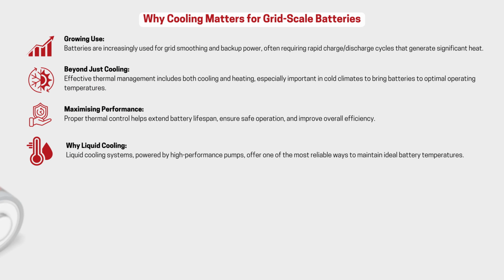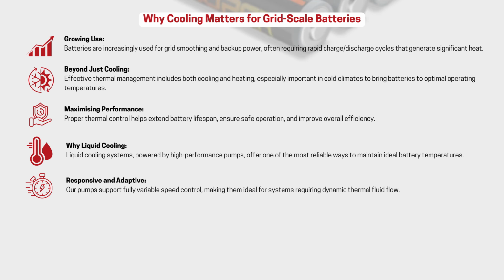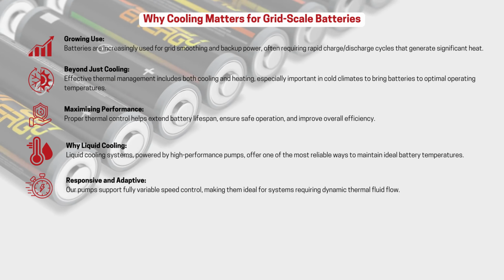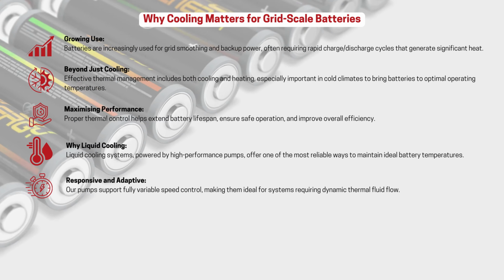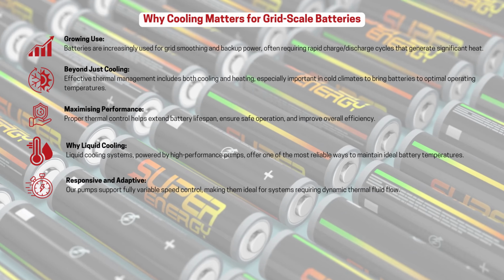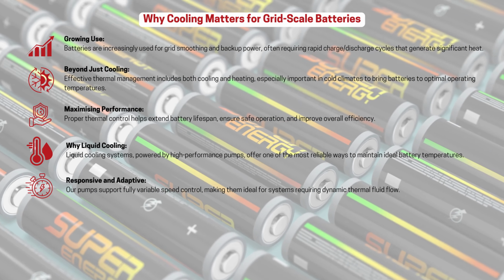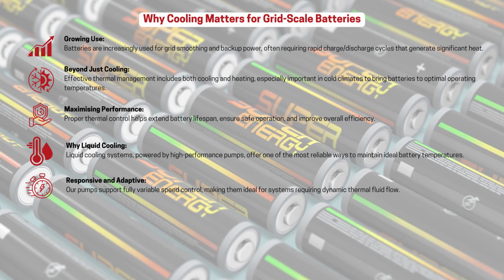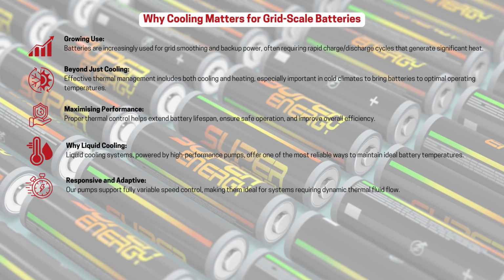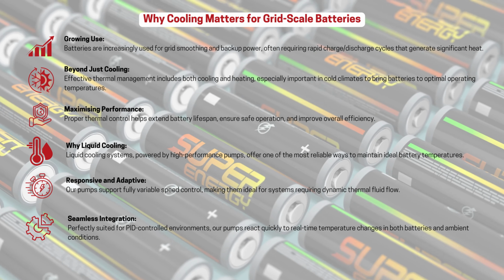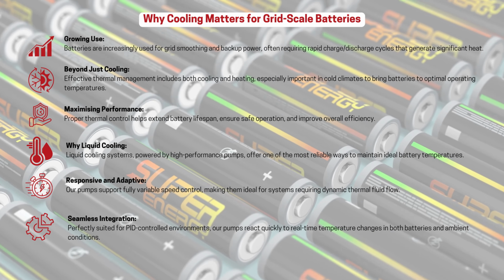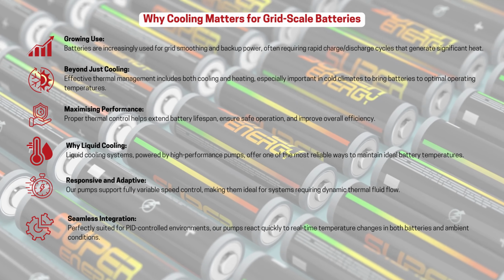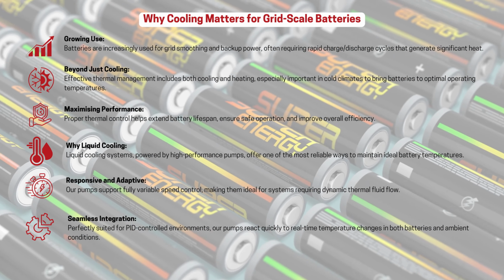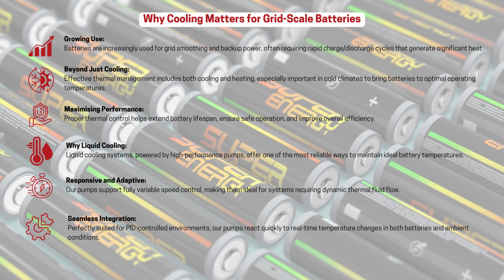We can see therefore that thermal management of batteries is a complex operation requiring quick response and variable flows of thermal fluids. Our pumps, having fully variable speed control, are ideally suited to fast response to your control system, which is likely to be a PID controller looking at temperature of the batteries and their operating environment.